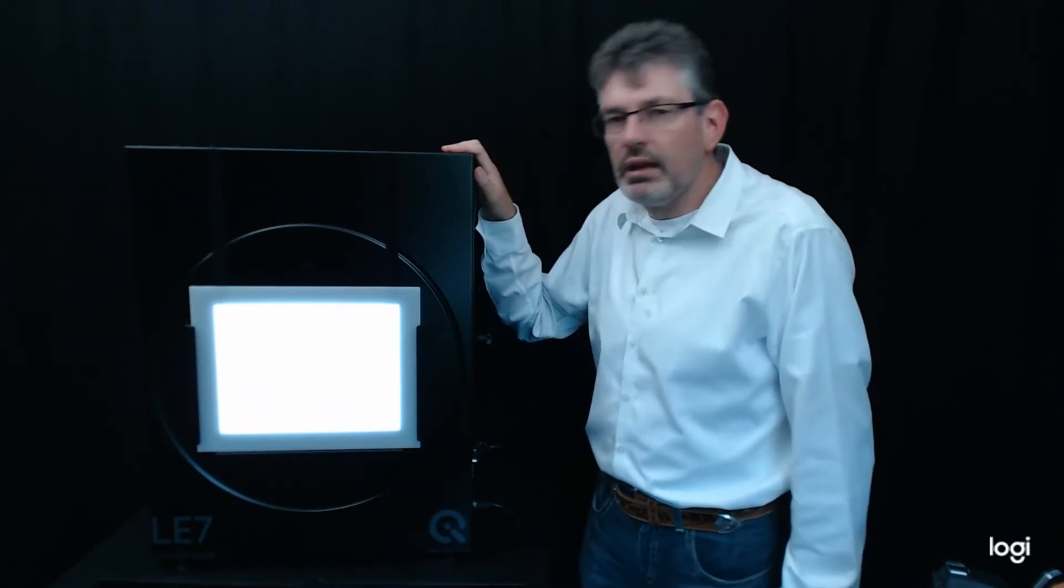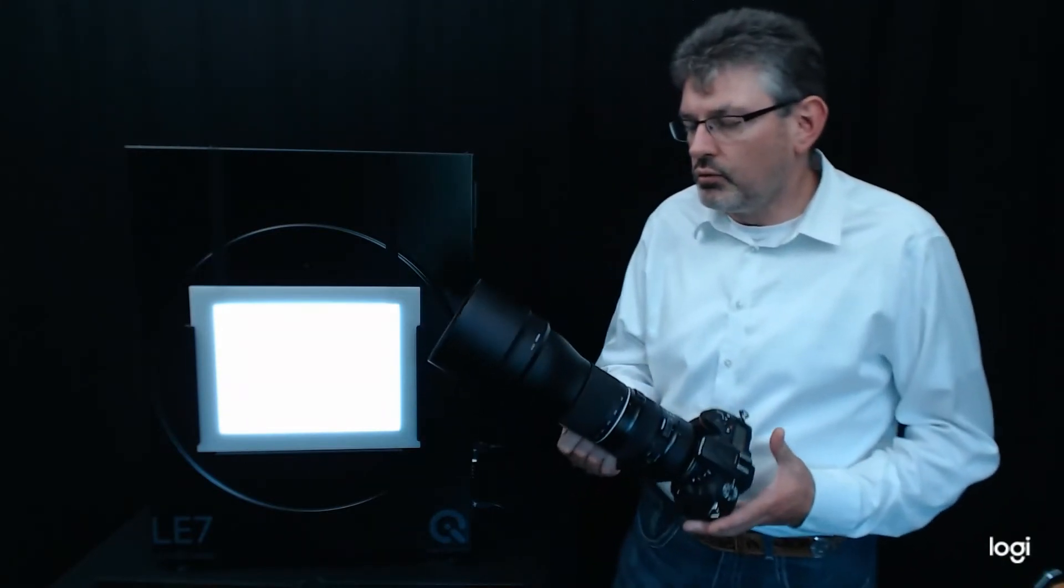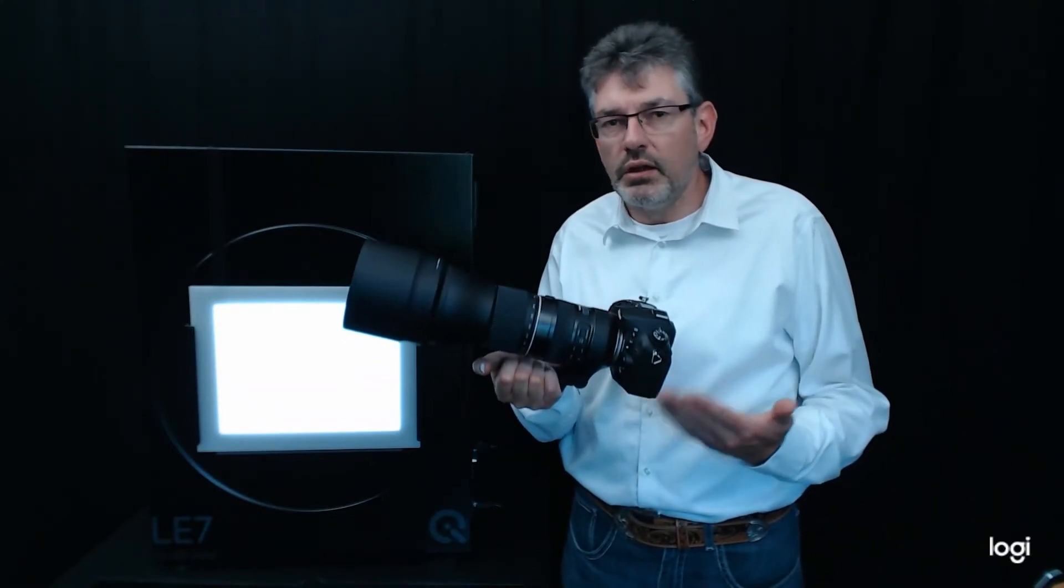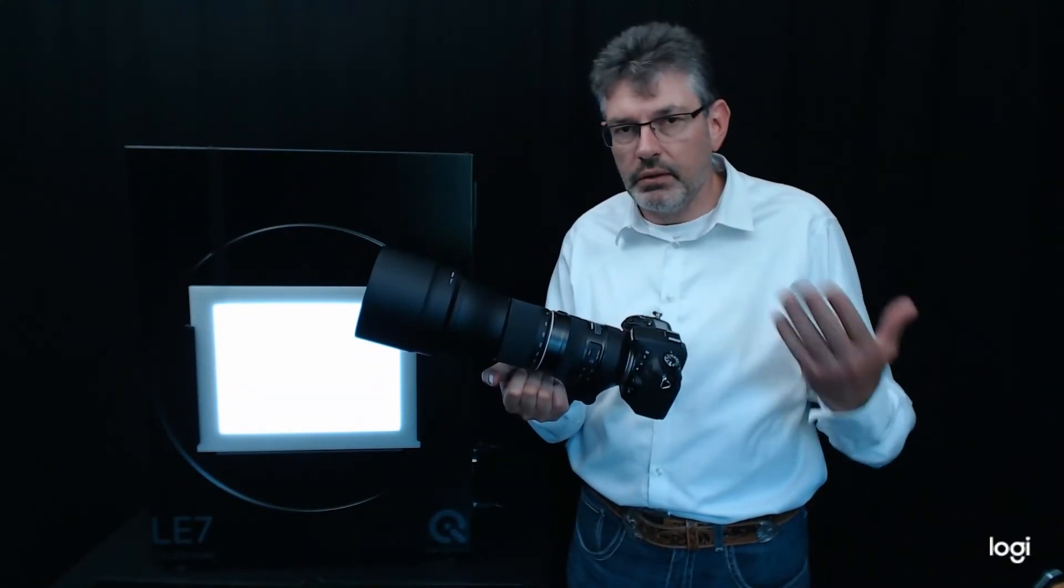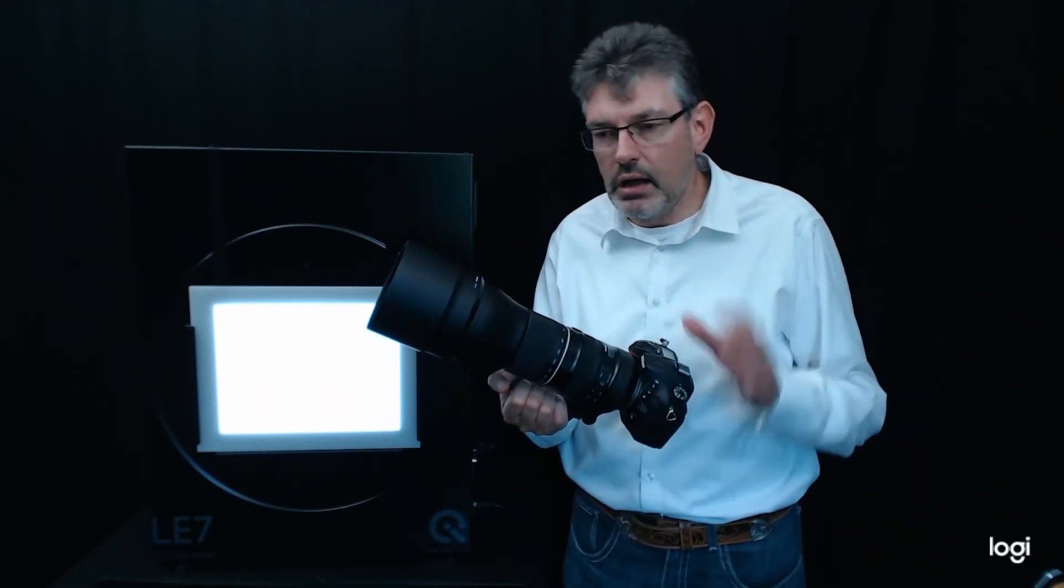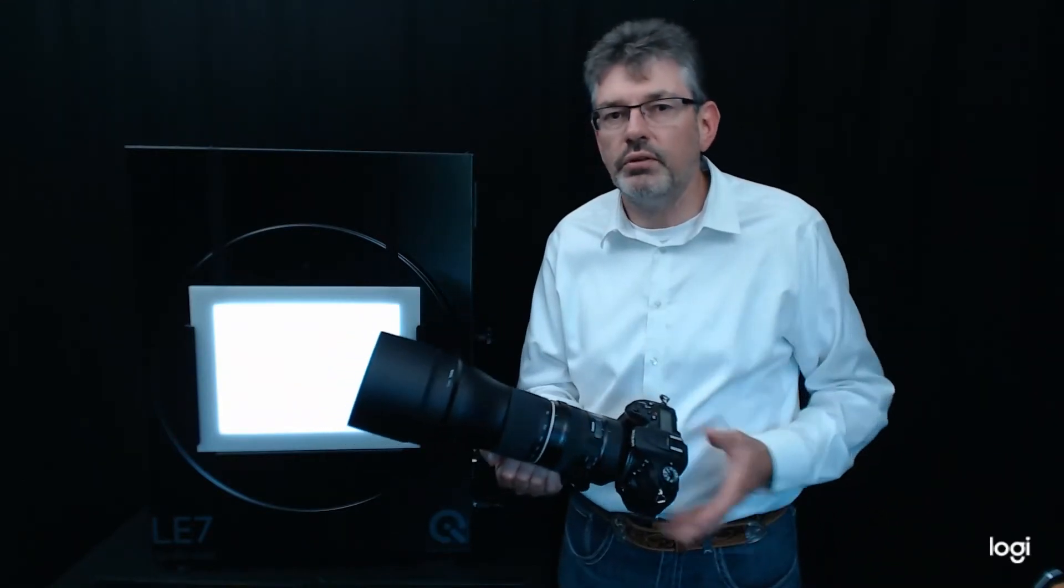Okay, what is the LE7 being used for? So one aspect is calibrating a camera. So for example, if you have a camera like this with a very big lens, all the other devices that we offer, the Cal devices, are too small on the output side. And therefore we need a larger output, which we can get with the LE7.